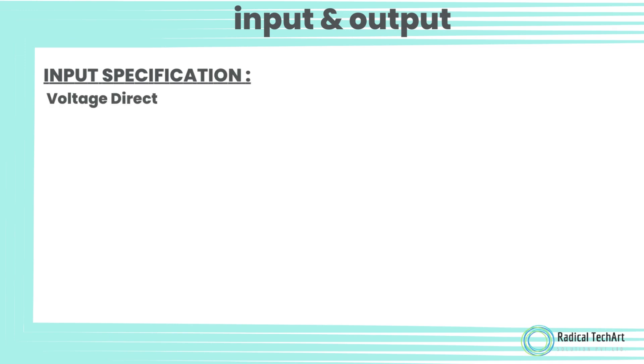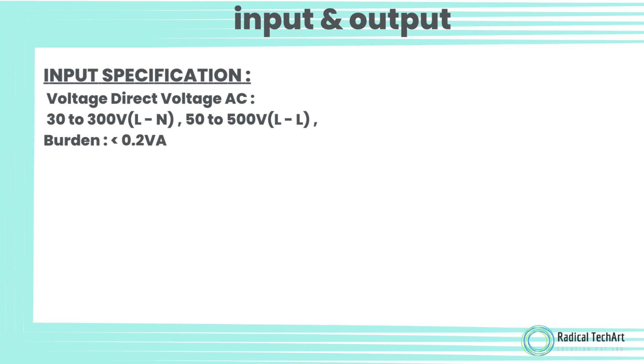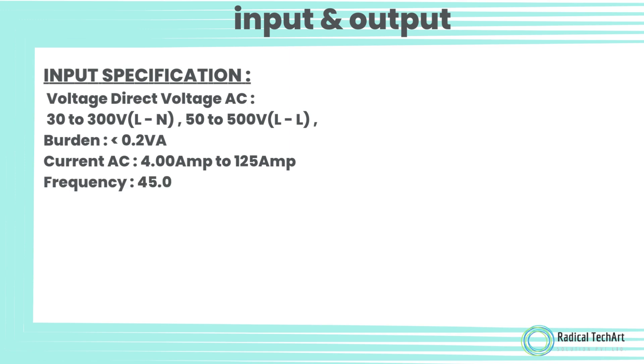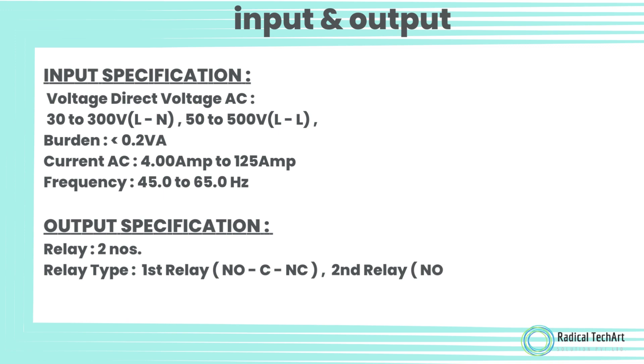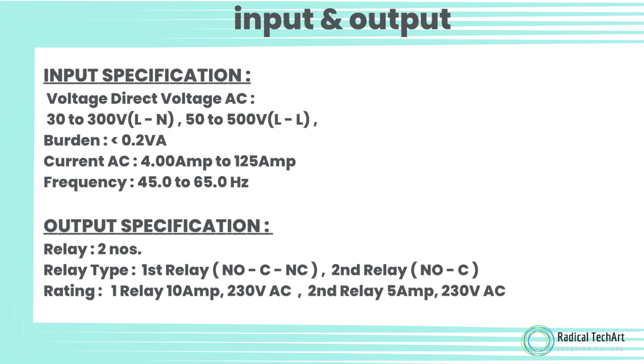Input Specification — Voltage: AC 30–300 Volt L-N, 50–500 Volt L-L; Burden: 0.2 VA. Current: AC 4 to 125 Ampere. Frequency: 45.0 to 65.0 Hertz. Output Specification — Relay: 2 numbers. Relay Type: 1st Relay NO/NC, 2nd Relay NO. Rating: 1st Relay 10 Ampere 230 Volt AC, 2nd Relay 5 Ampere 230 Volt AC.